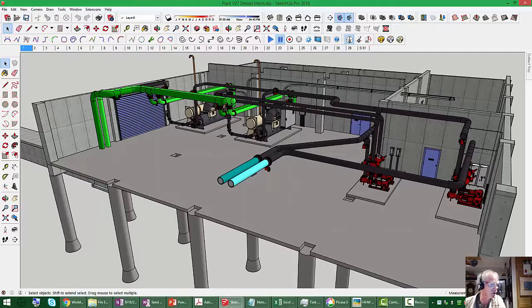If it was variable flow primary only, the pumps that pump the chiller would also be the pumps that are pumping the loop. So variable flow primary only at the plant might look like a constant flow plant. So you'd have to go out and look at the loads to be sure. The other thing you'd see in a variable flow primary only plant, probably in the plant, there'd be a bypass line like this from the supply header to the return header, but there'd be a control valve in it, and it would be after the pumps.